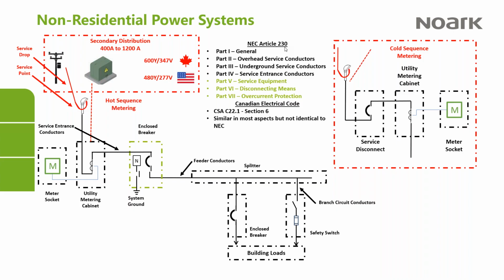I'm going to talk mostly about the National Electrical Code based in the US. The Canadian Electrical Code Section 6 is similar in most respects. It's not identical, but what I would say to you is that the Canadian code drives the same product requirements in an enclosed breaker. So if anyone has deeper questions on the Canadian code, we could set up a call another time.